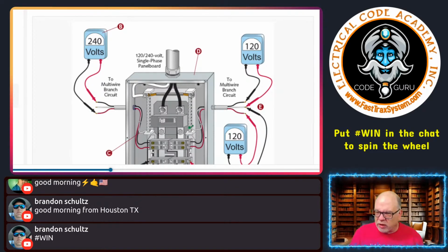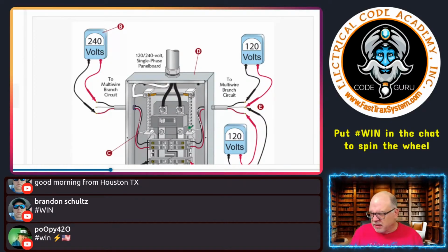In this case, since it's 120/240 volt, it's single phase, so it's just leg A to leg B, or line 1 to line 2. It's not phase to phase, because that would be a 3-phase panel. So here is black to white, 120, red to white, 120. So there you go, that truly is a neutral.